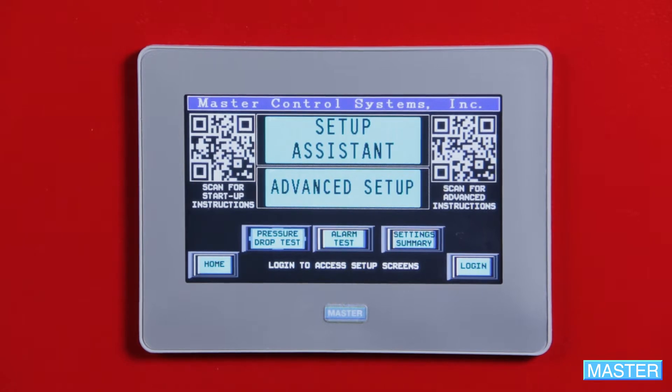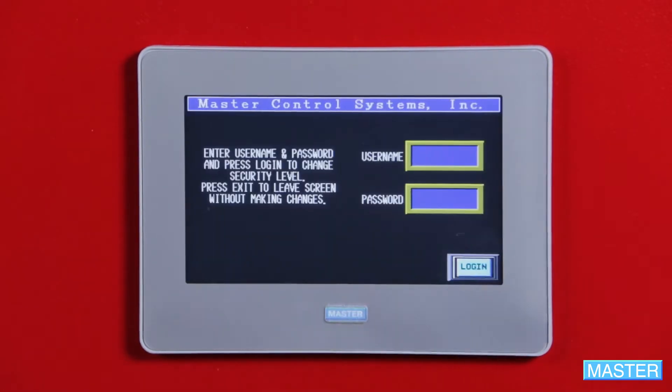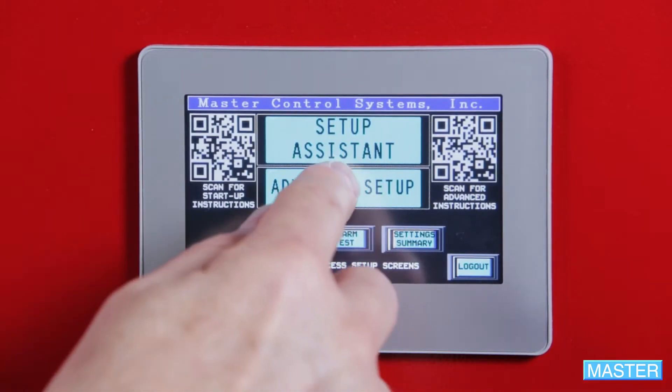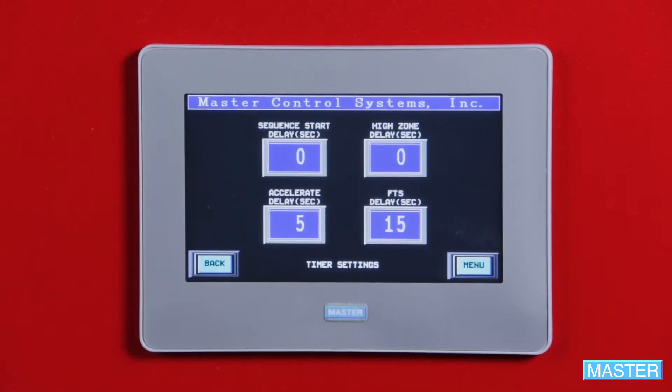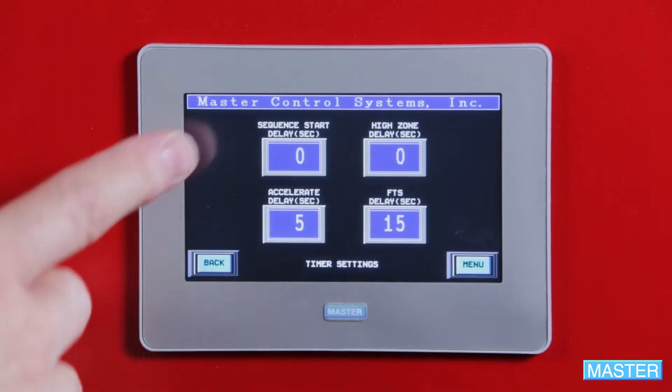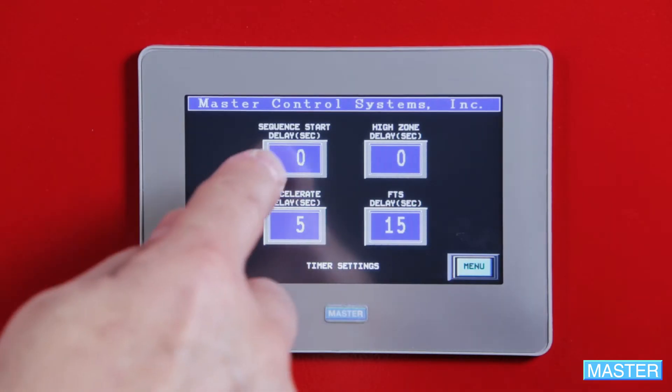Note the delay does not affect the start push button or remote start. To access the sequence start delay from the main screen, press setup, login using user user, advanced setup, and timer settings. The sequence delay has a range of 0 to 90 seconds, so simply push the sequence start delay button and enter the value you want.